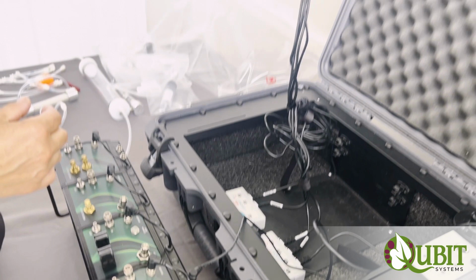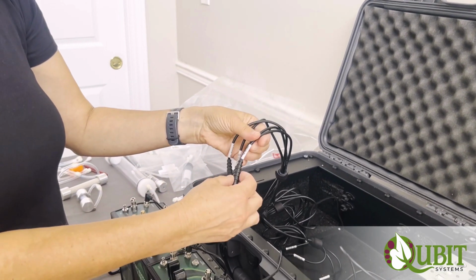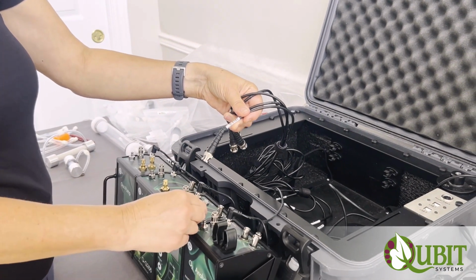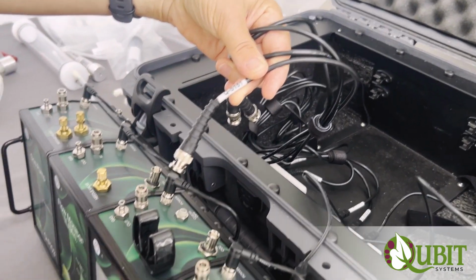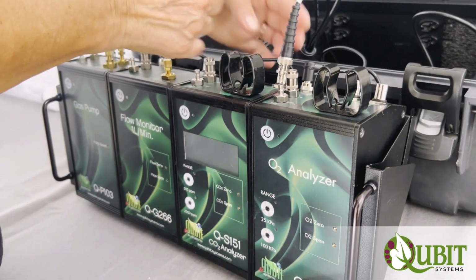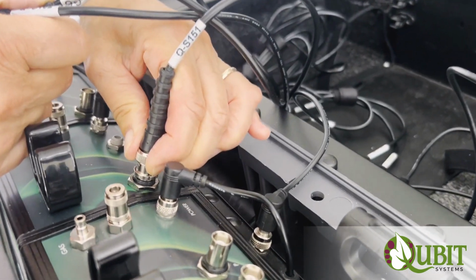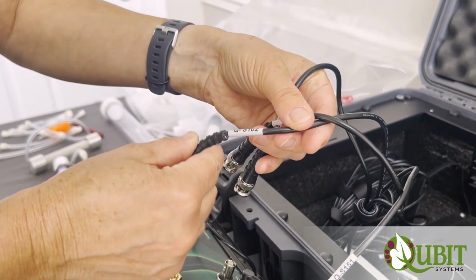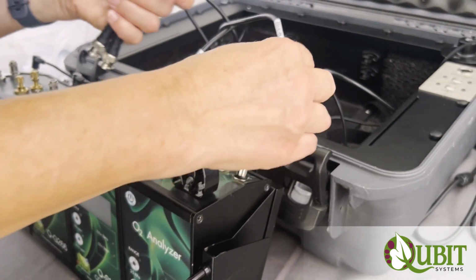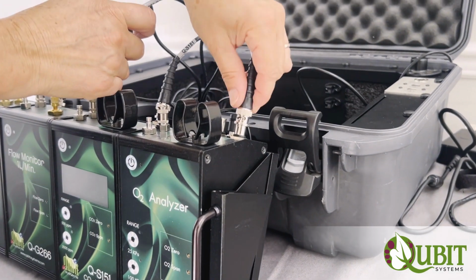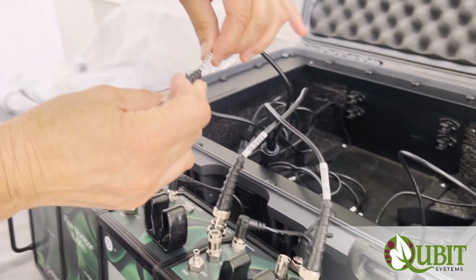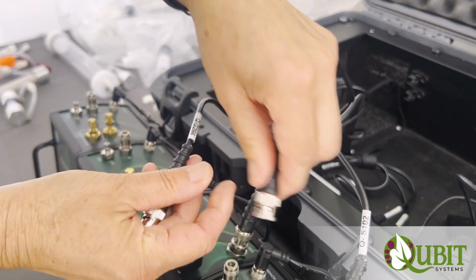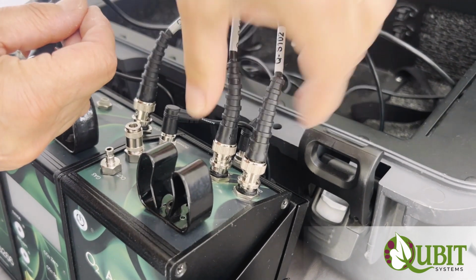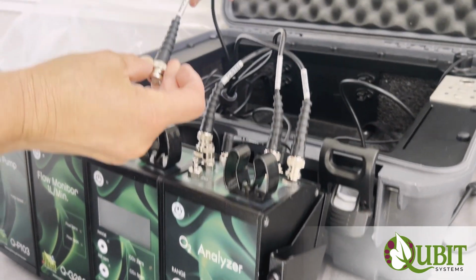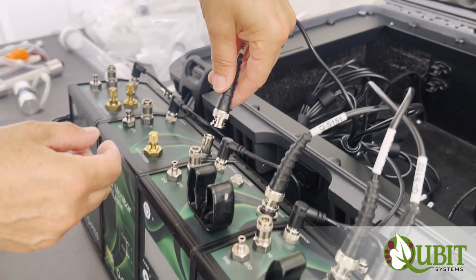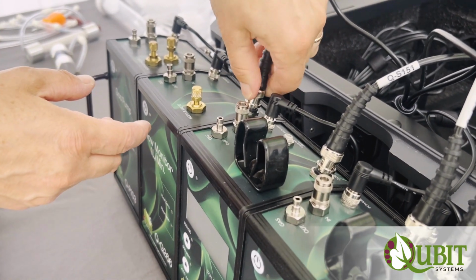Inside the Q Box, you will find all the data cables. They are already labeled, so you know which one goes with what sensor. QS151 is the CO2 analyzer. You would connect that, again, twist this to secure it. QS102 is the oxygen. You push it down, turn to secure. We have QS102P, which is the pressure sensor of the oxygen. Push it down, secure into place. And the final is the QG266, which is the flow monitor. Again, push it in, secure it in place.